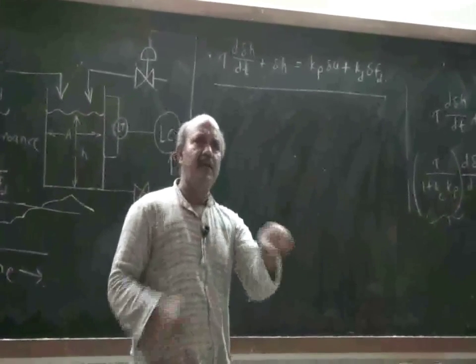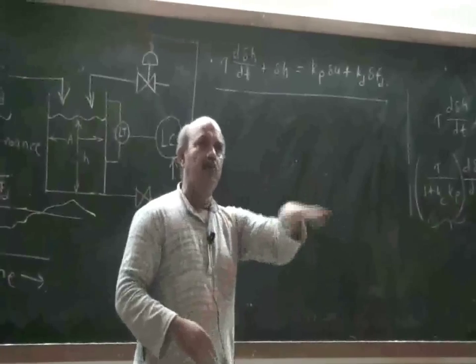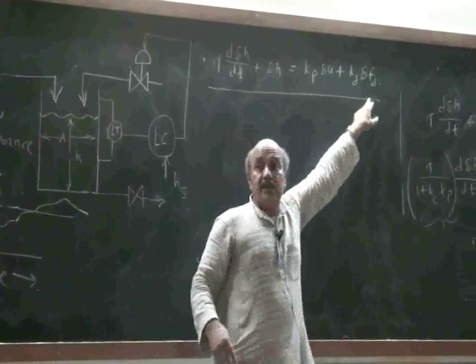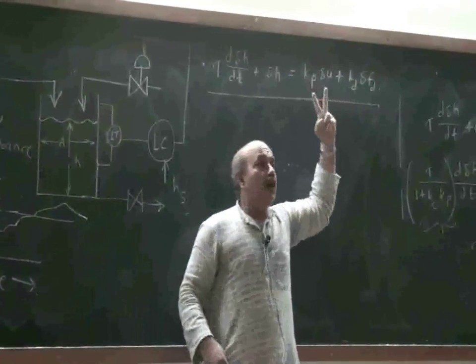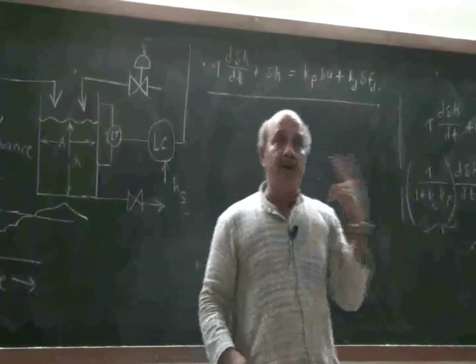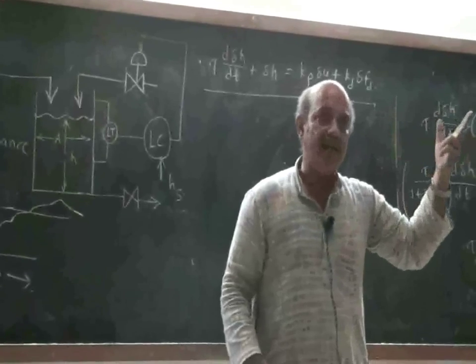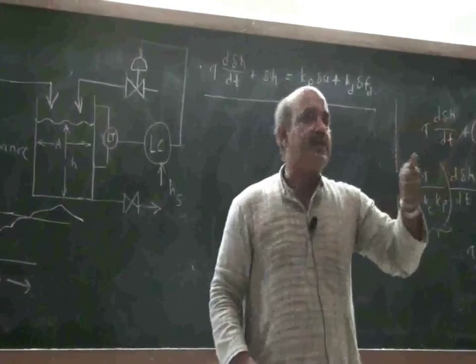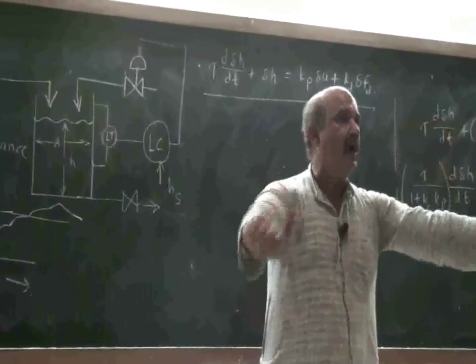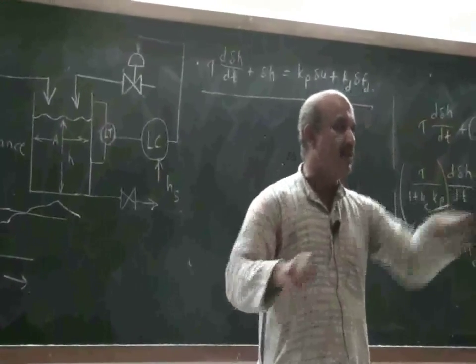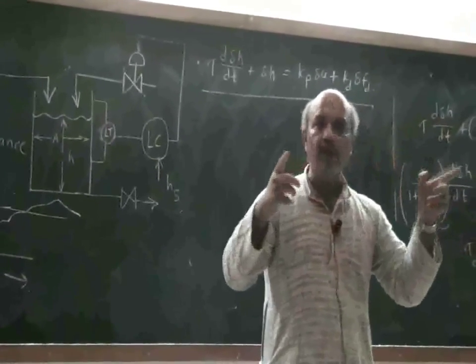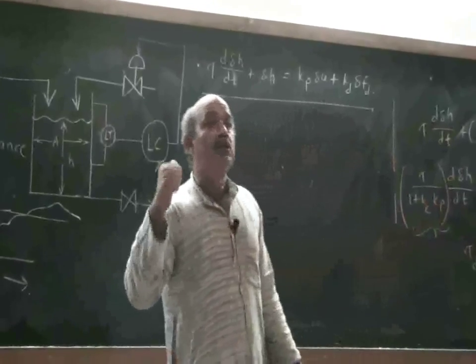If I change it slightly, how much it goes ahead. If I change it more, how much it goes ahead. These parameters, gains. So, if I want to drive a motorcycle, I just need two parameters: time scale and sensitivities. To do this, I do a test, which is a step test. I just give a step change, observe the behavior, develop a model. That's what we are going to do when you do the modeling part.